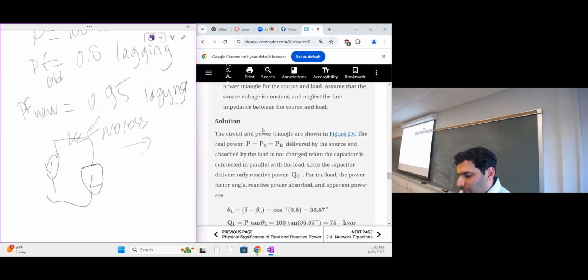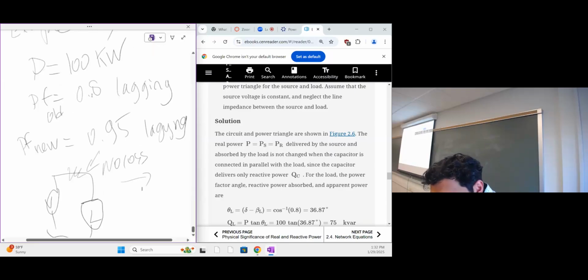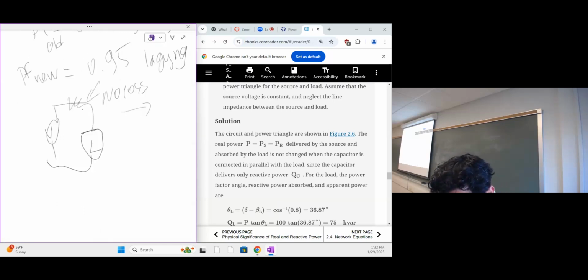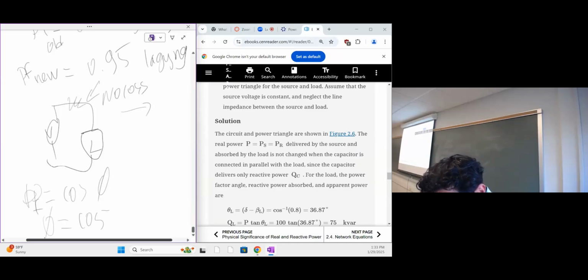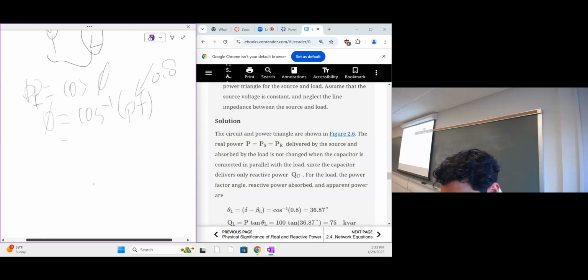So let's begin the calculation. The original power factor was 0.8. To get the angle, take the cosine inverse of 0.8, since power factor equals the cosine of the angle, so the angle equals the cosine inverse of the power factor. This gives us an initial angle for the load of 36.87 degrees.